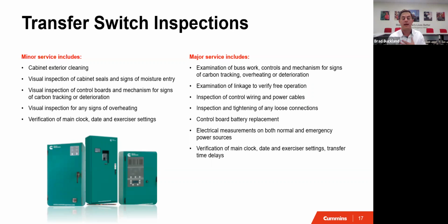Anything over 40 calories we can't operate on because we don't have enough safety equipment to handle the arc flash. Up to 40 we're good and can work around it. Everything else, we have to take the building off power in order to work on that ATS. So it gets inconvenient if that arc flash assessment isn't done, for us and for the customer - there's downtime, waiting on something to pass clearance, and potential liability in your building. The major service is when we have to de-energize the building - we're actually getting into the nuts and bolts and tightening things, and it's more extensive. It's not required or even recommended for this small of an application or for condominiums. Once you get to larger systems, you want those checked out, since there's more incident energy behind there and more likelihood of a problem.